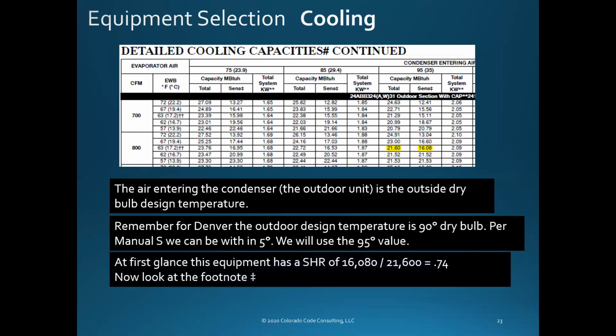So if you guys were doing this, these are exactly the numbers you would use. You wouldn't have to worry so much about excess latent capacity unless you were really dry. We'd have a sensible heat ratio - you take the sensible capacity and divide it by the total capacity, that's how you get the sensible heat ratio. In this case it's about 0.74. In our example, we want to get as close to 1 as we possibly can. We're not going to find equipment that gets to 1, but we're going to get closer.